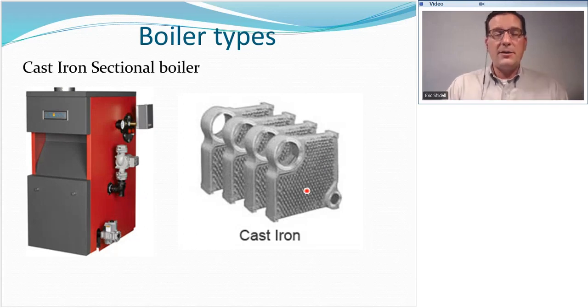Cast iron sectional boilers really aren't a whole lot to look at. They look like just a boring sheet metal box, and here's a pretty standard-looking cast iron sectional boiler. Cast iron sectionals are the oldest type of boiler that has ever been out there. They were one of the first ones created. The very, very first boiler was actually made of pipes welded together. And then shortly after that, they came up with the casting technology to build these cast iron boilers. And we're talking back in the 1800s is when these boilers were developed.